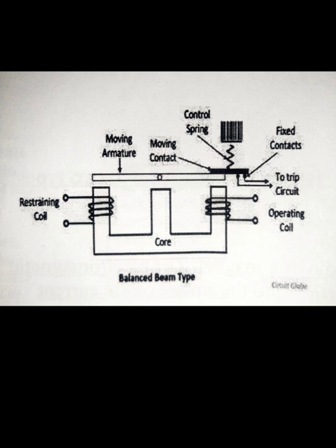In the electromagnetic attraction relay, the armature is attracted to the pole of the magnet, and the electromagnetic force exerted on the moving element is proportional to the square of the current flowing through the coil. This relay responds to both alternating and direct current.